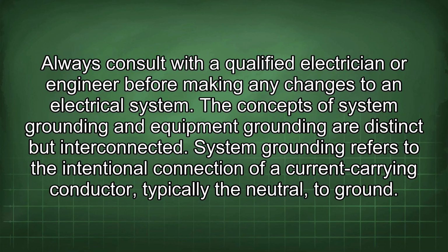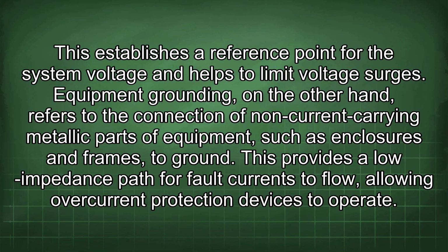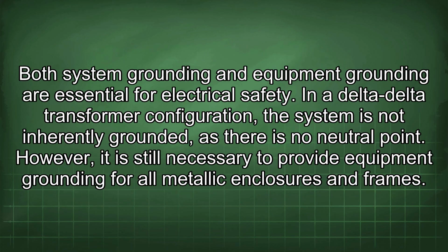The concepts of system grounding and equipment grounding are distinct but interconnected. System grounding refers to the intentional connection of a current-carrying conductor, typically the neutral, to ground. This establishes a reference point for the system voltage and helps to limit voltage surges. Equipment grounding, on the other hand, refers to the connection of non-current carrying metallic parts of equipment, such as enclosures and frames, to ground. This provides a low impedance path for fault currents to flow, allowing overcurrent protection devices to operate. Both system grounding and equipment grounding are essential for electrical safety.